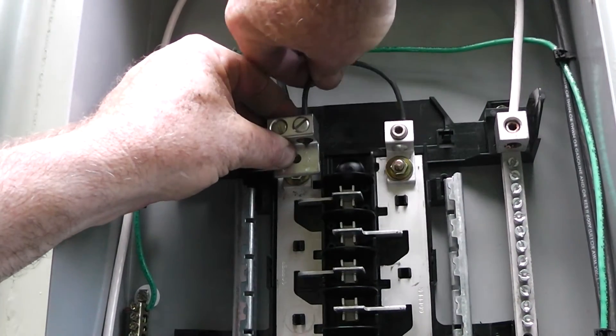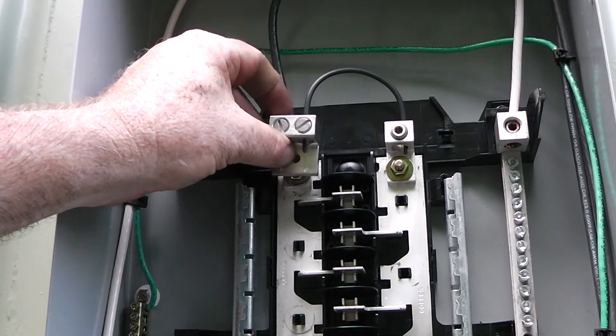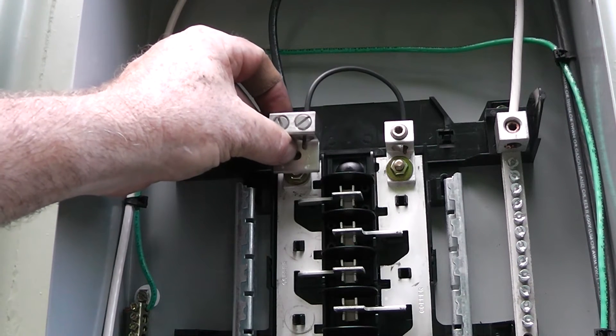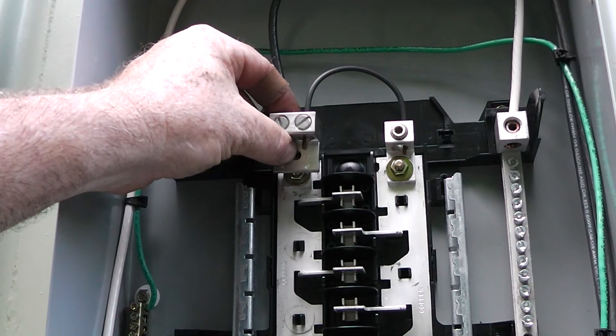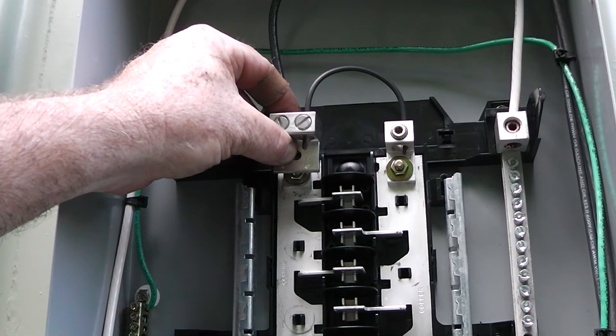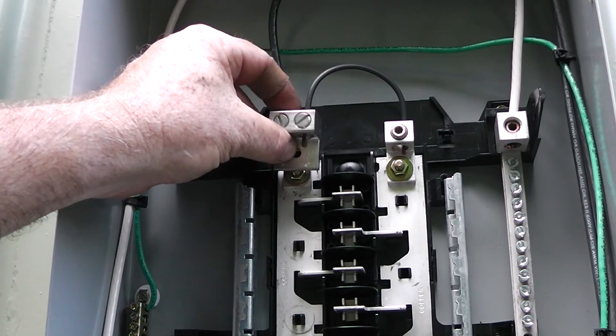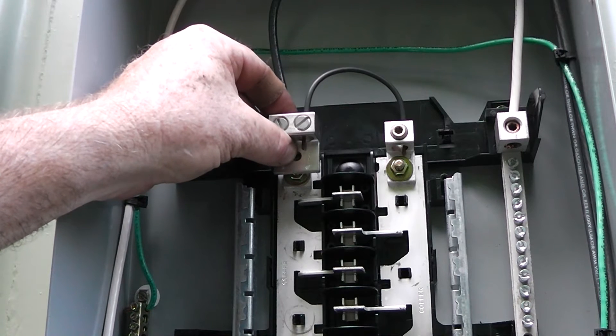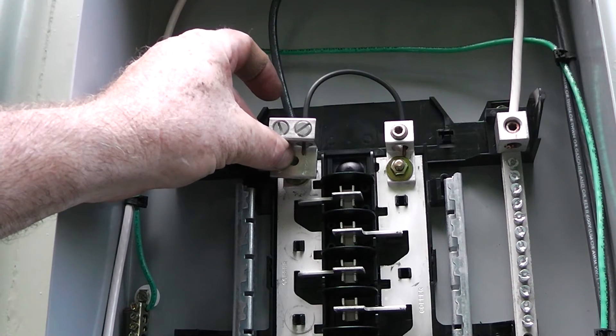We put double lugs in all the time, especially on meter sockets. We don't usually jump them out for 110 volts. Now the authority having jurisdiction might say it's not legal to have a 120 volt panel, that's their interpretation of the code. But I really don't see any problem with doing it like this.